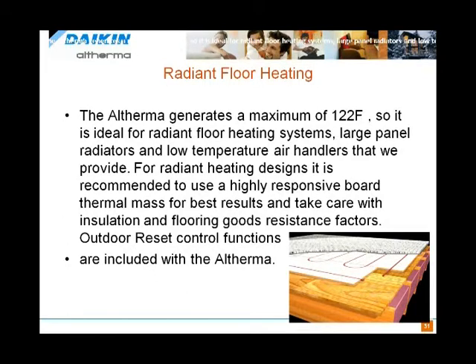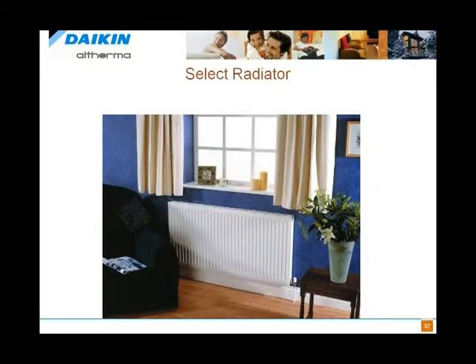We can use radiators. With the temperatures we're supplying on these units, you have to just about double the surface area in order to be able to use the lower supply water temperatures, but it can be a very economic way of going. And again, we will be introducing soon a relatively 110 to 120 degree baseboard design out of Europe that could also be attractive in this regard and very price attractive.